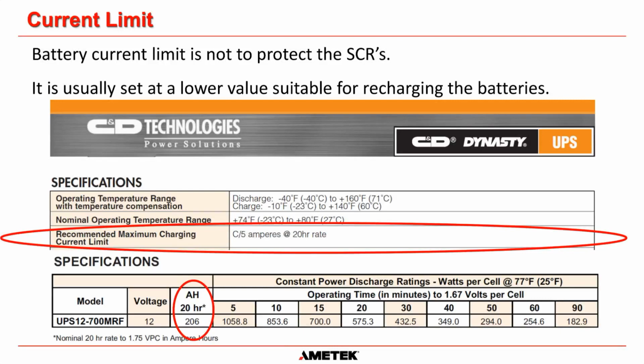Okay, but what C&D are saying is the recommended maximum charging current limit should be C5 of the 20-hour rate. C divided by 5, okay? So in other words, what they're saying is the 20-hour rate for this battery is 206 amps. So they're saying that you should limit the current to this battery to around about 41.5 amps. To me, that doesn't make sense. Now, the battery manufacturers may have a good reason, but if the battery can supply 100 amps, why on earth can't the battery accept 100 amps in charge? I think what they're trying to do is make sure that the charging process doesn't overheat the battery, which can cause thermal issues inside the battery, which can cause thermal runaway eventually. That's what they're probably trying to do.